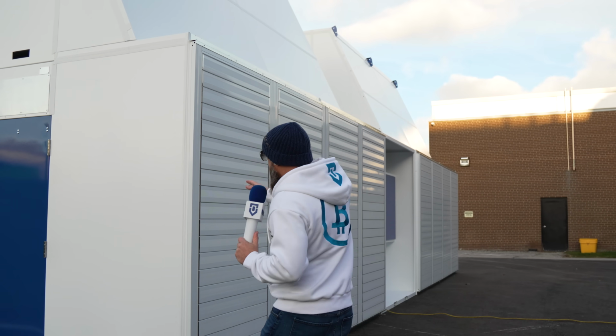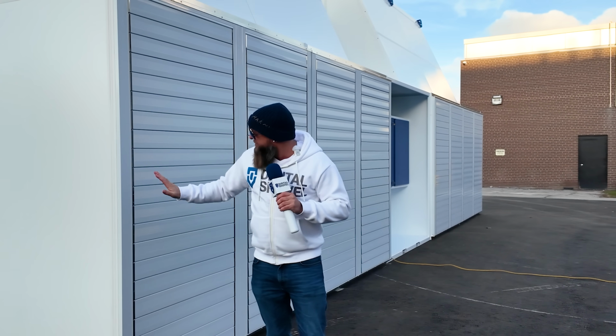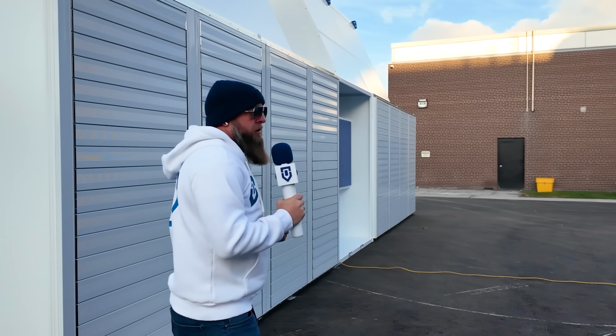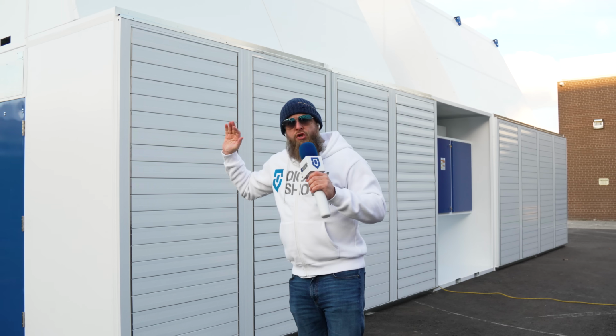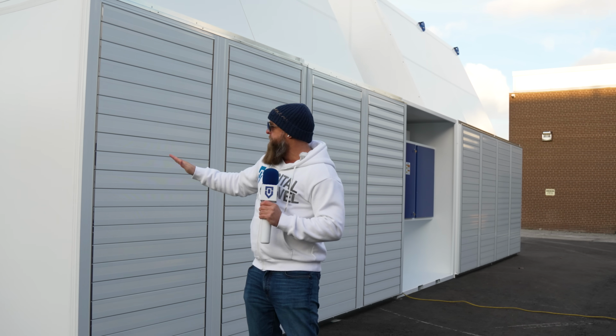We've got a louver system here at the back, which is electronically controlled. Obviously right now this is not hooked up with miners in it, so it's closed. During the winter, they will open just a fraction, or if it's really cold, you can tell them to stay closed to get that hot air recirculating. During the day when it's hot, these louvers will actually open up to 110 degrees, so they will point up slightly. The pods have a rain sensor on them, so that's able to tell if it's raining. They will then slightly close to force that hot air down and prevent rain from being able to penetrate into the pod and open back up automatically.